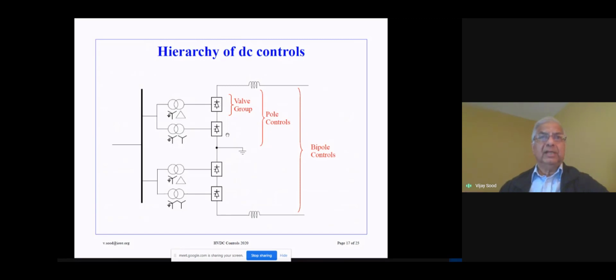Over here, you can see the two valve groups. The controls which are tied with this valve group are the valve group controls. These controls which operate on both the valve groups are indicated as pole controls. And then finally we have the bipole control. So this is a bipole, so the positive pole and the negative pole, the neutral connection. So this is the positive pole, negative pole, and this operation which takes place over the whole bipole. These are the bipole controllers.